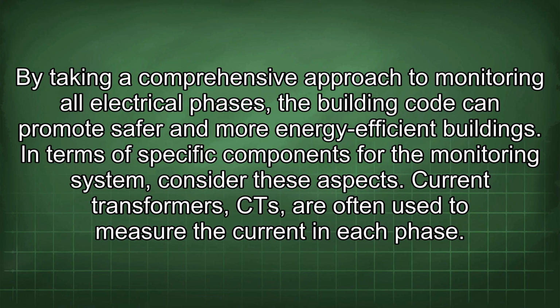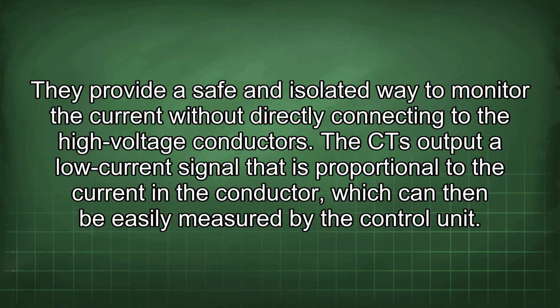Current transformers, CTs, are often used to measure the current in each phase. They provide a safe and isolated way to monitor the current without directly connecting to the high-voltage conductors. The CT outputs a low current signal that is proportional to the current in the conductor, which can then be easily measured by the control unit.